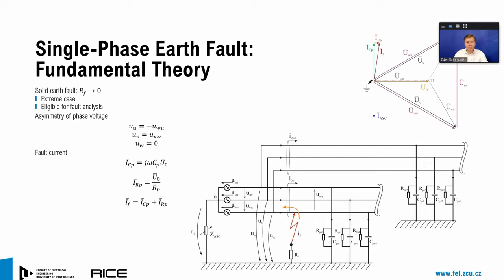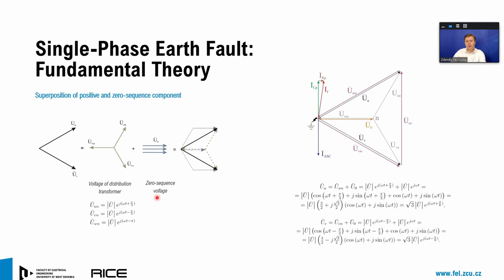I think all of you are very familiar with single phase earth fault theory. Just to remind you, if we operate insulated or high impedance grounded power distribution grids, the earth fault means that there exists a conductive path between one of the grid phases and the ground. The fault current flowing to the place of the fault has two components, a capacitive component and an active component. We need to work with that, and we are trying to mitigate the fault current in the system so that we are still able to operate the grid under the earth fault.